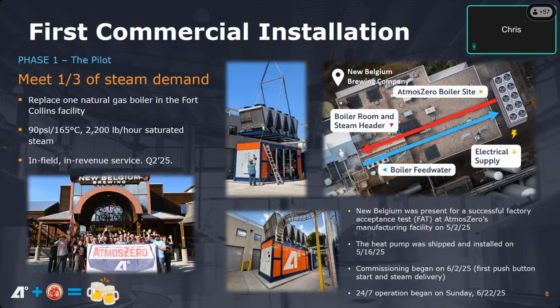This is New Belgium. If you've been following AtmosZero for any time, I'm sure you've heard about this project. We are taking a third of the steam demand of the facility away from gas and putting it on a base load of our AtmosZero heat pump design. Again, this is a tiny bit smaller unit. This is a 650 kilowatt unit.